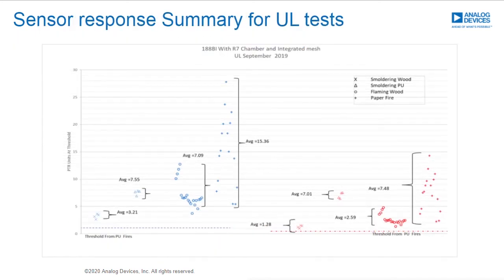This slide here just shows the sensor response summary for all of the UL tests. At the bottom you have the dashed line where we would set our threshold based on that flaming polyurethane fire, high enough that you don't trigger on the hamburger. And all of the other different types of smokes fall well above this threshold. So you see your smoldering wood, your smoldering polyurethane, your flaming wood, and your paper fire. And they all fall well above the threshold that you would set based on the polyurethane.